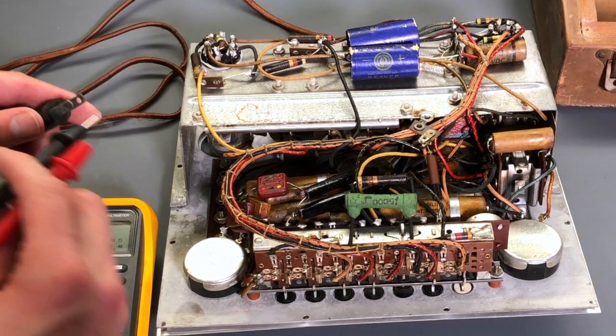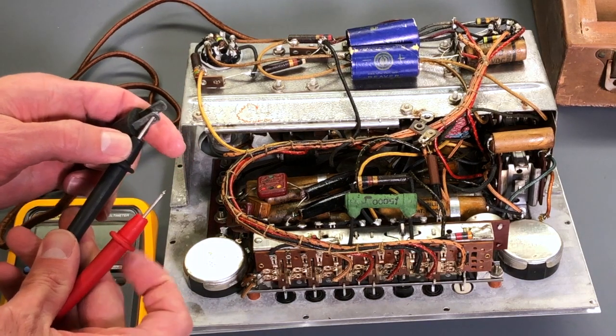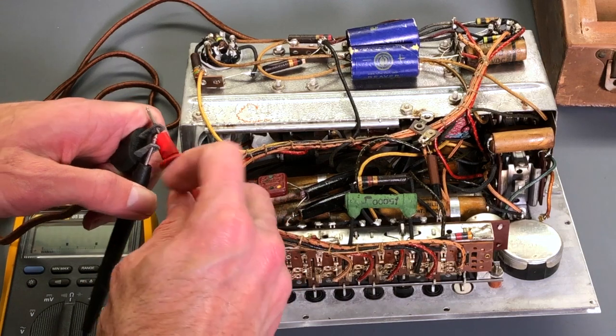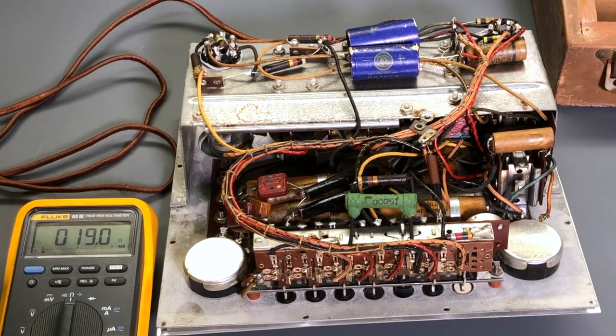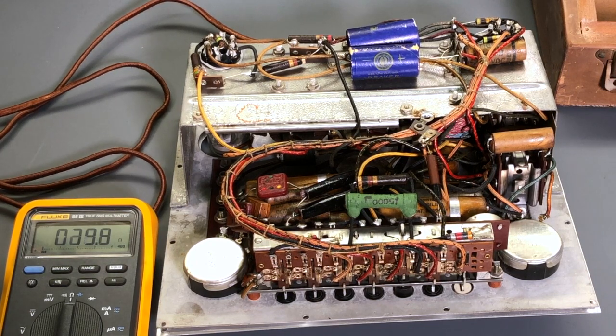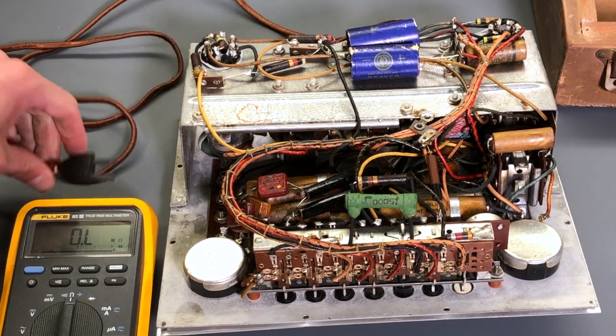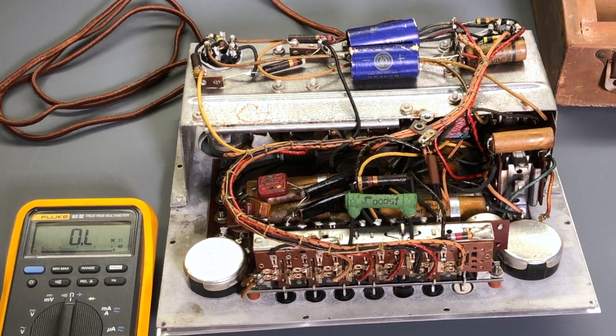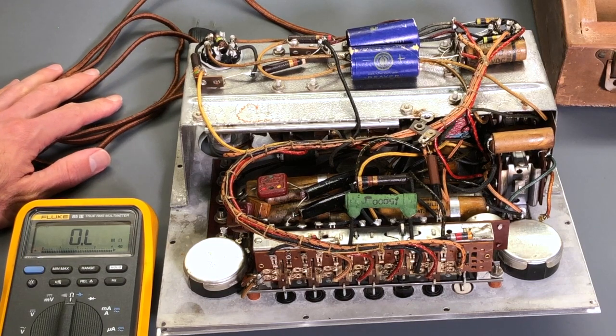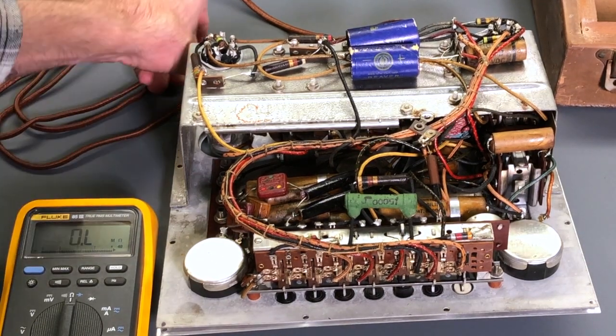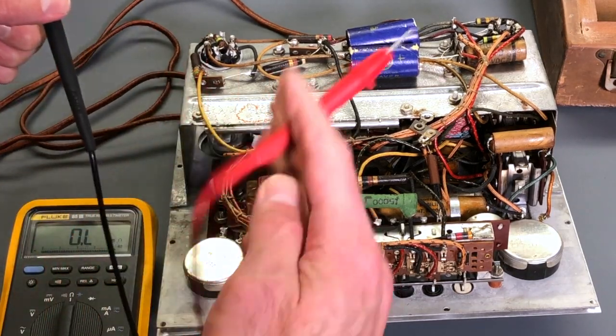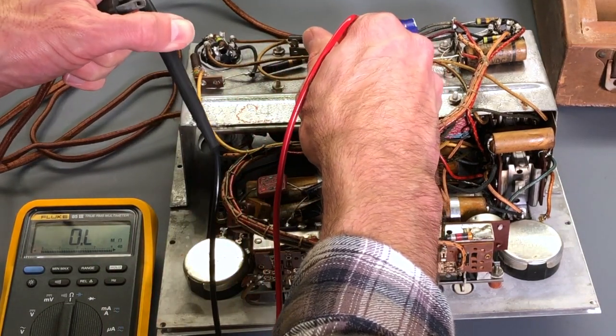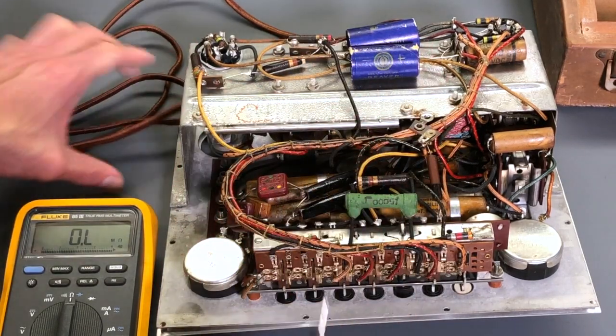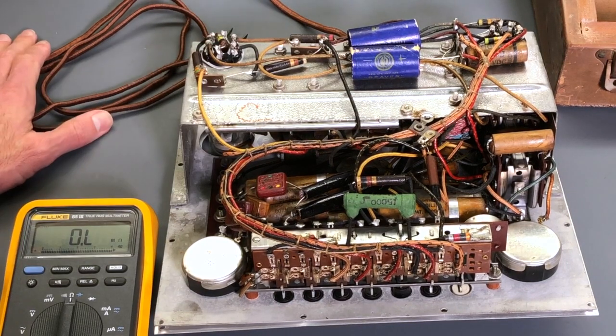So with the ohm meter, we'll start by going across the plug over here like so. So you can see the ohm meter is reading right about 19 to 20 ohms, settles right in there. So that's reasonable. That's the primary winding on the power transformer. So no short circuits in the cord, so that's a good thing to see. Another test here. Let's check from the cord over to the chassis just to make sure we don't have anything going on there. Looks good. Open circuit. And looks like that's an open circuit, so that's good. So no short circuits between the line cord and the chassis.